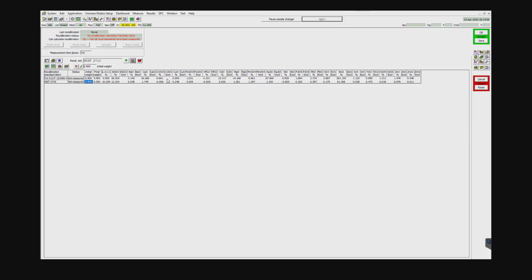Another thing you want to be cautious of is in the application calibration itself, if you excluded points, they will show up here in whatever curve that you were looking at. So let's say, for example, if you excluded calcium, this sample from the standards, if you included a standard in the recal samples here on this table, it would show an X, which means if there's an X here, exclude, it's not going to use this measurement to do calcium oxide correction, okay?